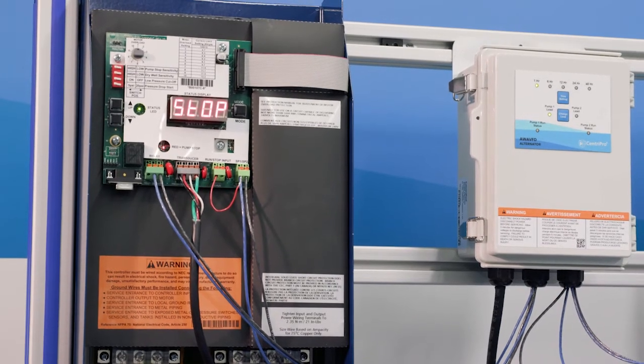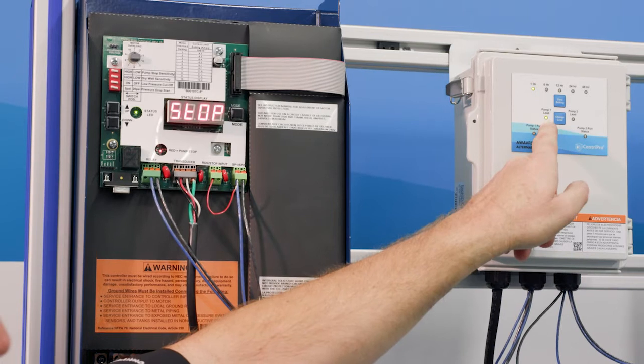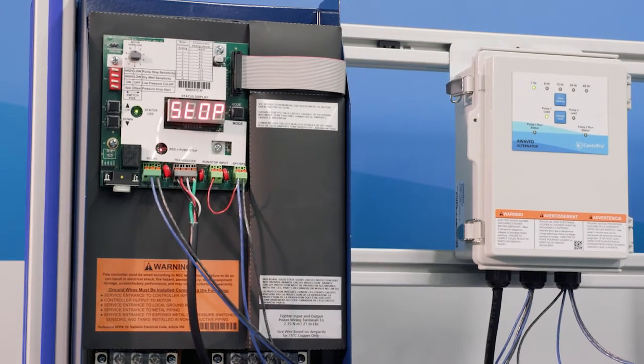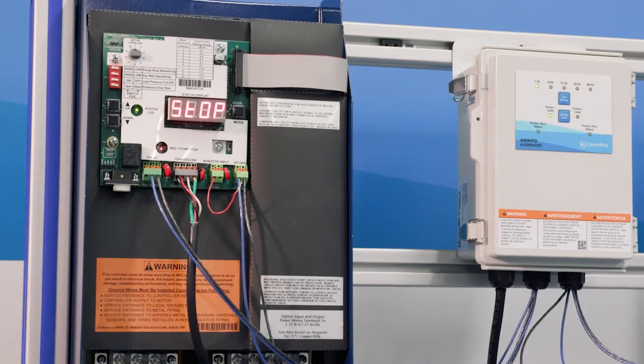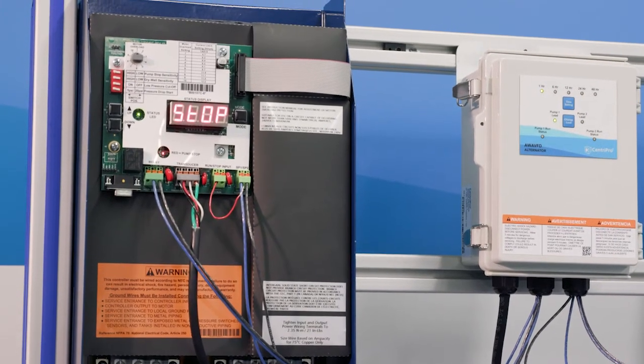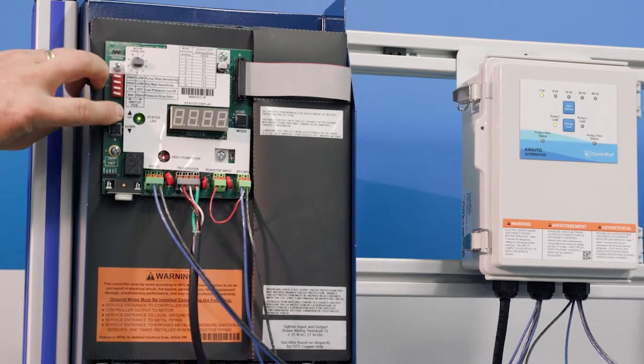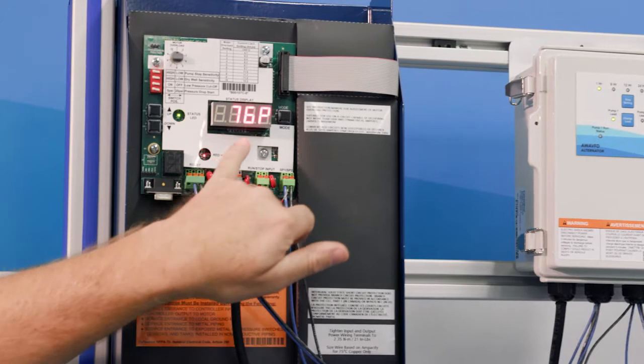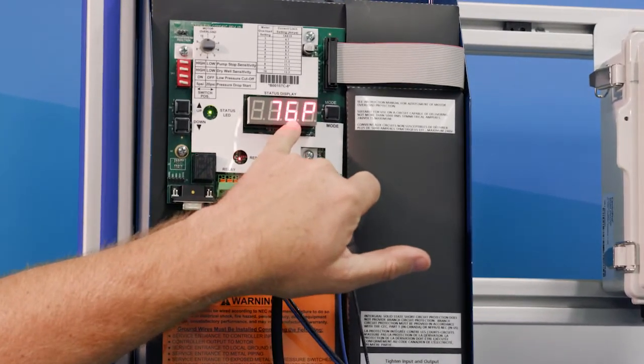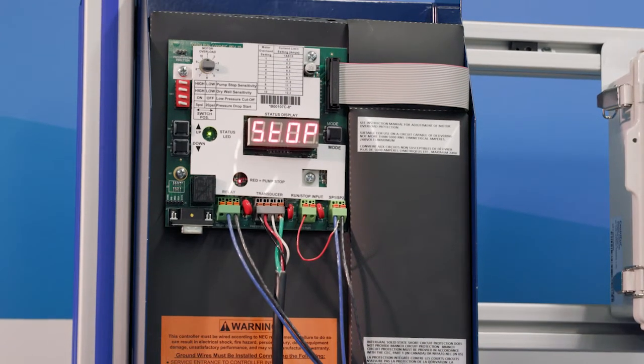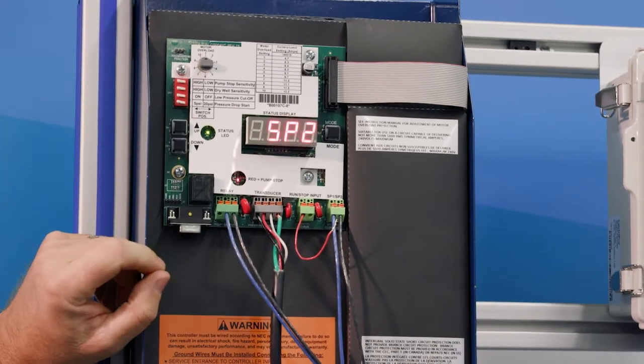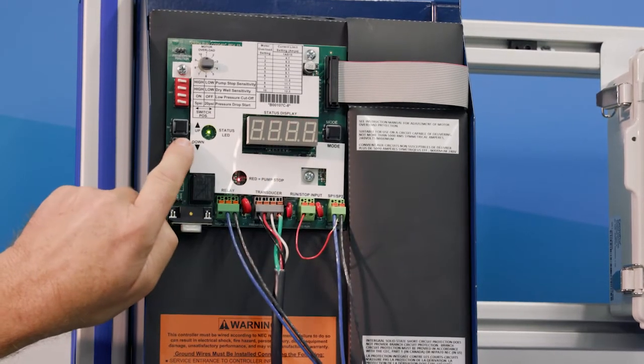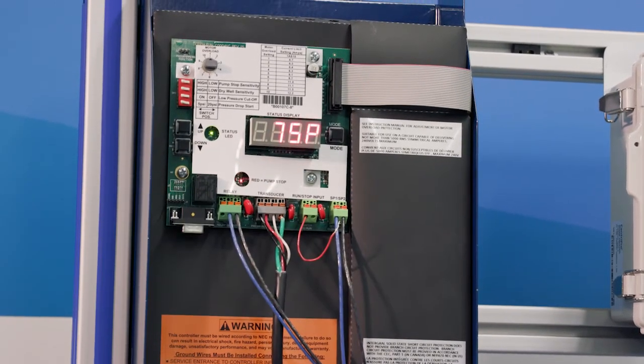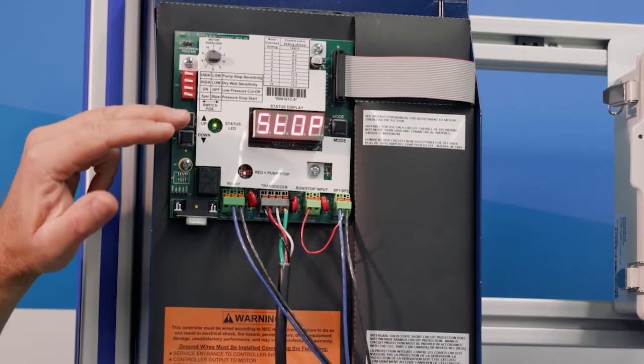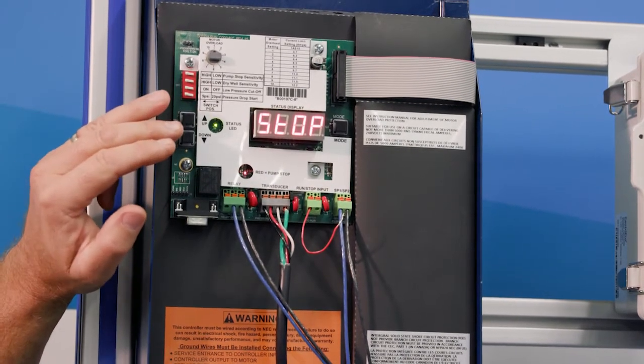So how do you set those? So again, we're going to start off with number 1 as our lead. And I've got this disconnected here, so it's not going to run. And now I can set my SP1 and SP2. So simply press and hold for a second. And why is it saying SP2? Because SP2 is the lead, right? So just do it again, SP2. As long as that's blinking, we can change that. So we're going to increase it or decrease it. And let's go with 75. Okay, so now SP2, which is the lead, is set to 75 psi.